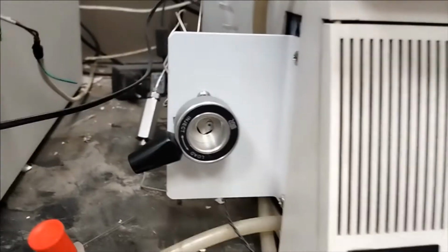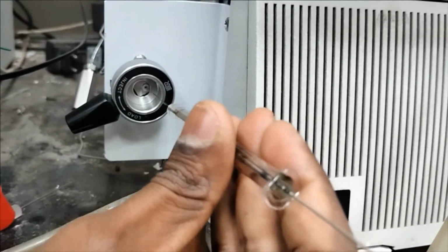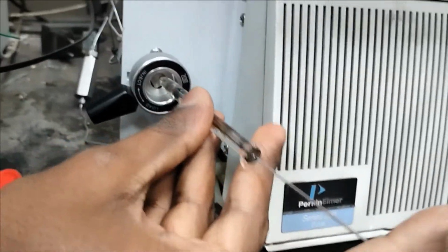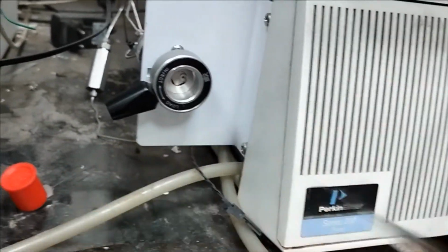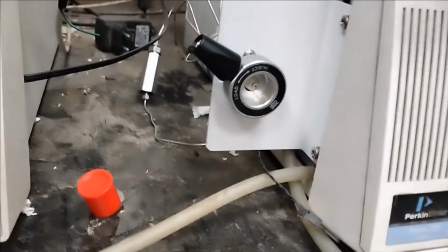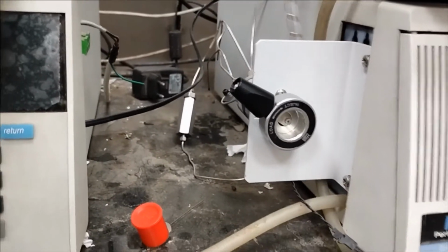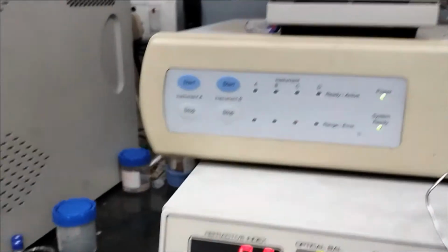Now this is the injection port. You have to inject exactly like this. So this is the injection mode. Once you have injected this, you have to lift that knob up, and that condition is called as a load condition. Now I have loaded the sample. Now the pump would be taking the sample and the mobile phase together to that particular column. We have started the analysis.